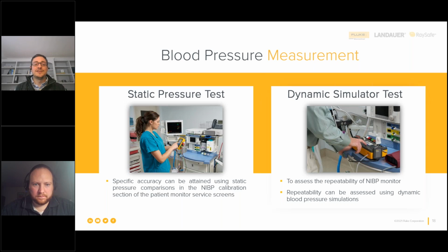NIBP, non-invasive blood pressure, can be tested using static pressure, right? So this could be pressure generated by a bulb and measured by a pressure meter, or using an automated patient simulator. And the other way you could do it is dynamically, right? So you can use a simulation using an NIBP patient simulator. So there are 2 different types, static and dynamic. Typically, the specific accuracy has only been assessed by the use of static pressure measurements. These measurements are very straightforward, very easy to understand, but the NIBP of a patient isn't static.